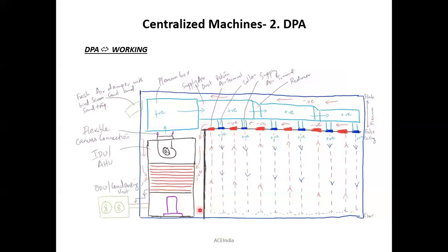Now you can see. So, all right, let's talk about the connection of this entire DPA with the duct system. We studied that this machine is a top discharge type. That means it will provide supply air in a top discharge manner itself, isn't it? So as the cold air is supplied in a top discharge manner, in order to accommodate this one, we need a small connection piece called a plenum box. The purpose of the plenum box is not only to accommodate the air, but also to split the air according to the direction wherever you want.